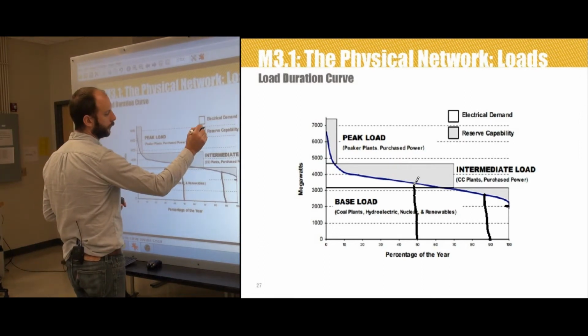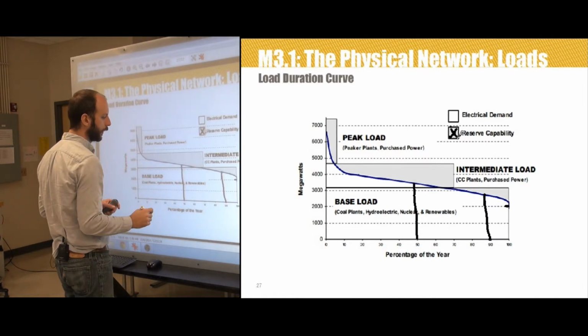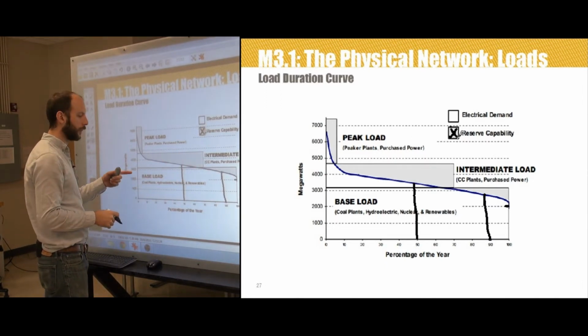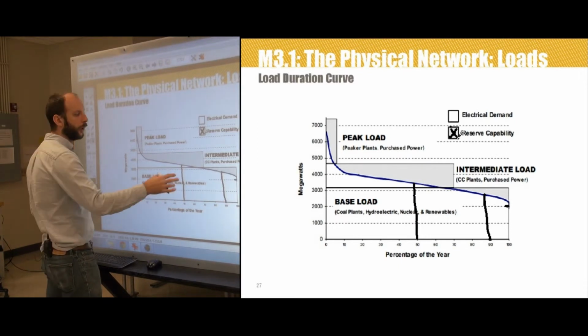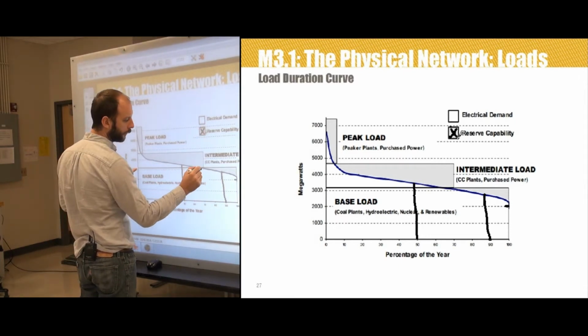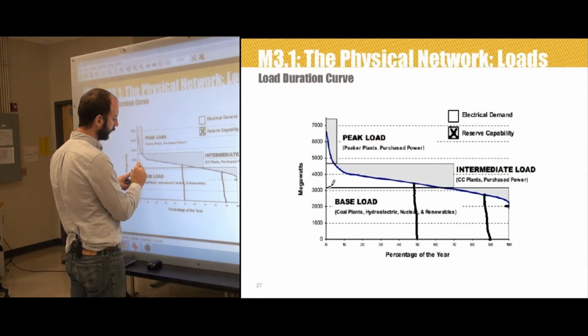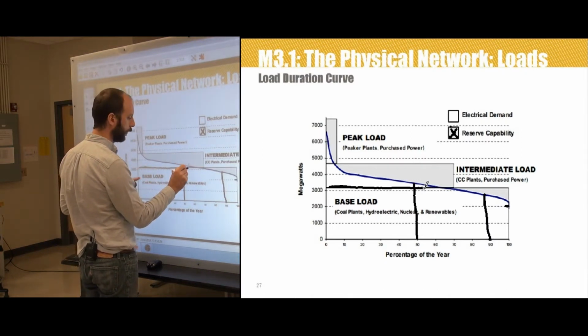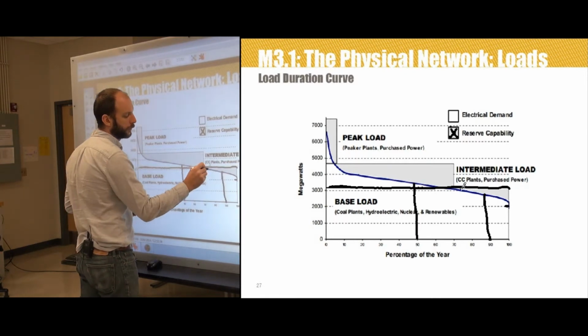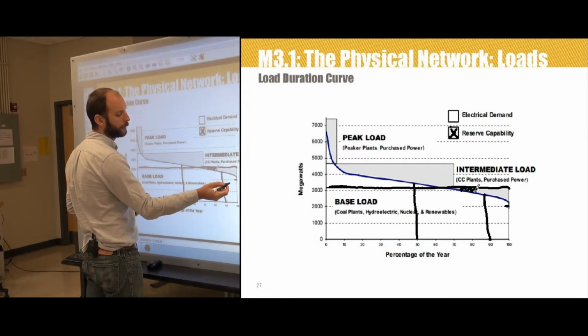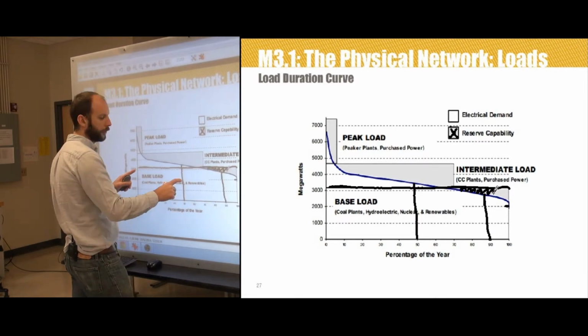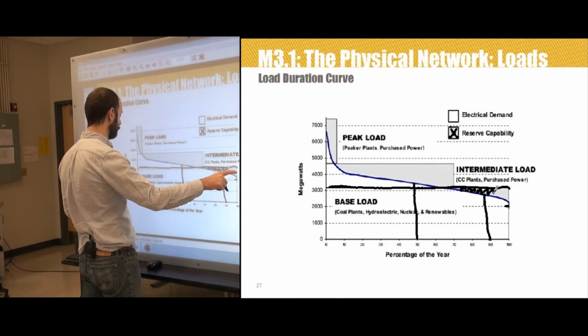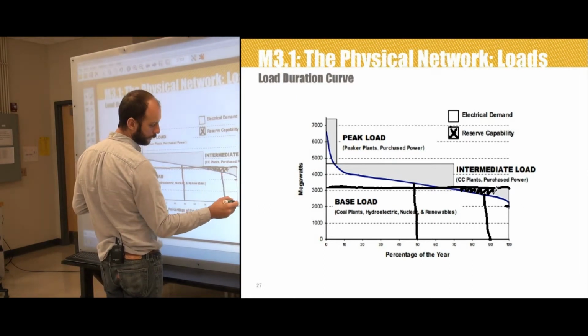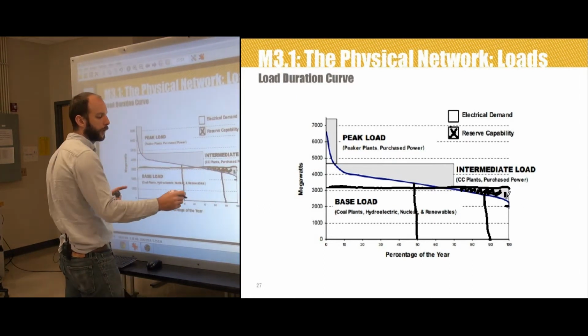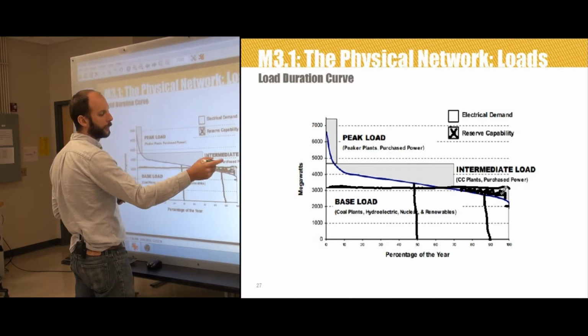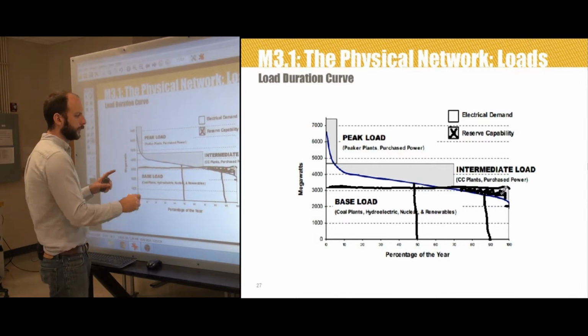So we've also introduced two new terms here: reserve capability and electric demand. Electric demand is how much demand there is on the system by the customers. Reserve capability is the difference between what my base load can provide, which is about 3,100 megawatts, and how much is actually being used. So my base load power plants are capable of producing 3,100 megawatts of power, and during part of the year, or part of the day, I'm not using all of that, so I can sell that off. It's my reserve capacity.